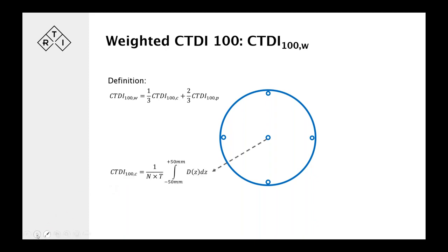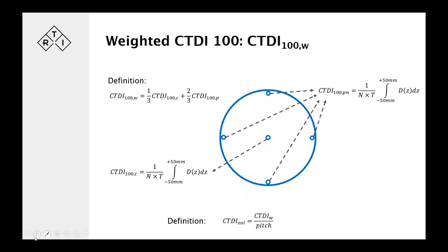And the way it's done is, of course, we look at the CTDI 100 with the pencil ion chamber in the center hole, make one axial scan without moving the table, and integrate the dose. With a pencil ion chamber, you just read the dose value, of course. From the peripheral holes, we do the same. So those are the formulas, and that's the CTDI weighted.